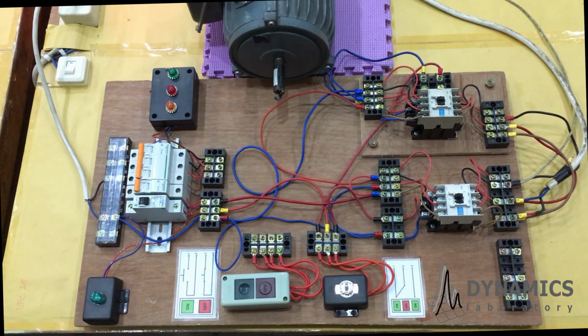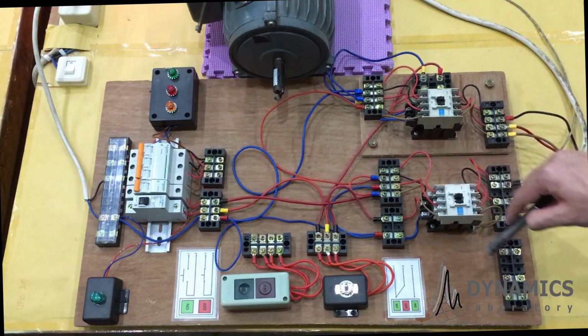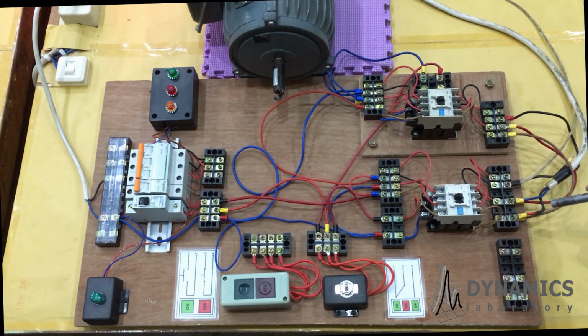Let's see the load circuit. The load circuit in contactor 1 is the same as previous. You can see the sequence. In here, I have already connected the main winding from the AC motor and also auxiliary winding. Red cable, blue cable of main winding, and auxiliary winding. Or if you refer to the module, then this is cable 1, cable 2, and cable 6.